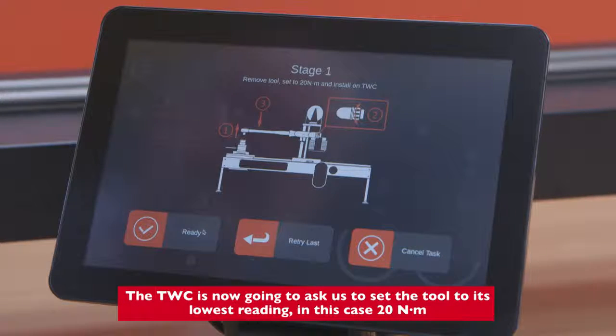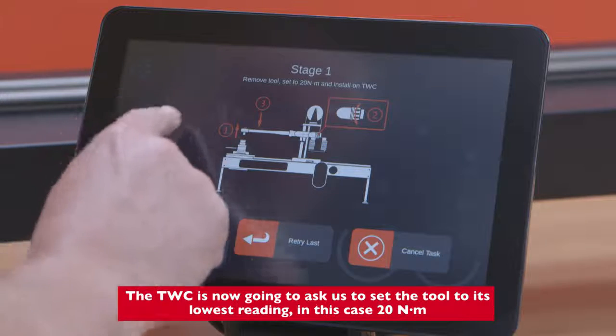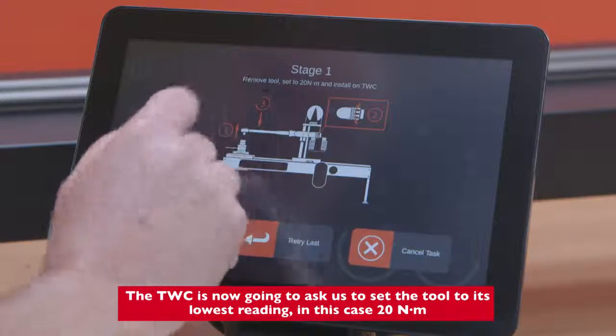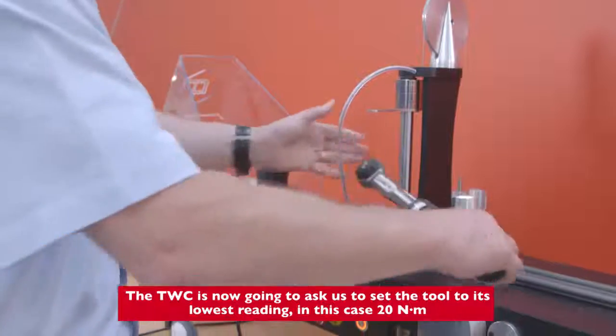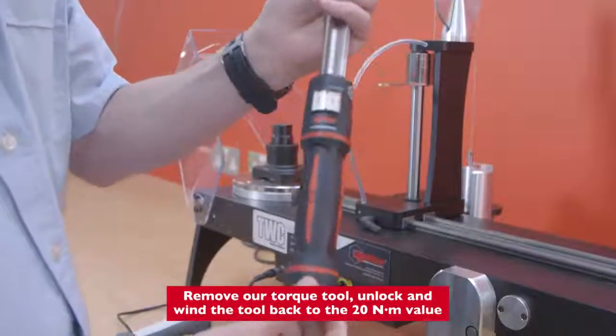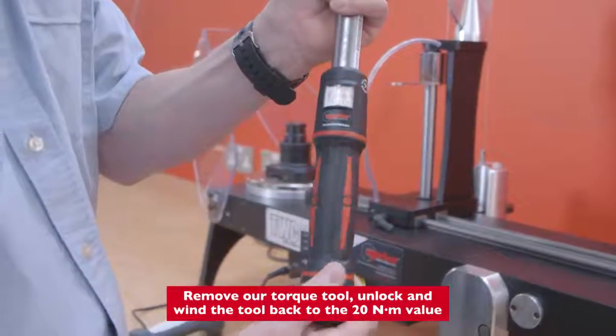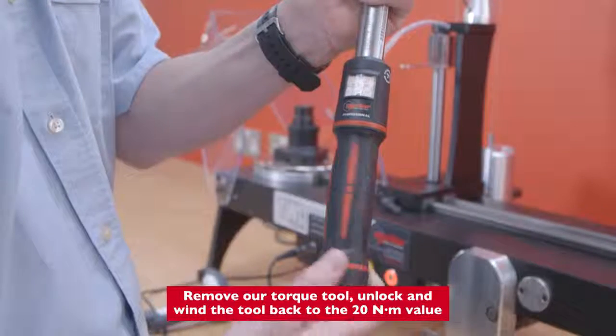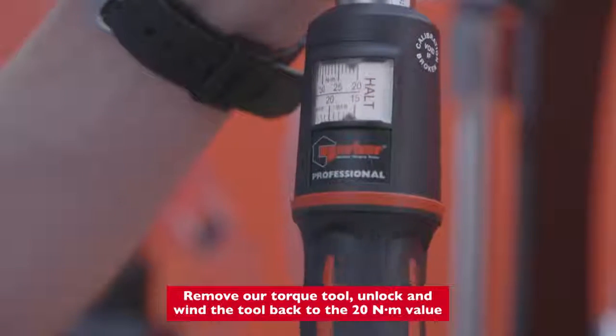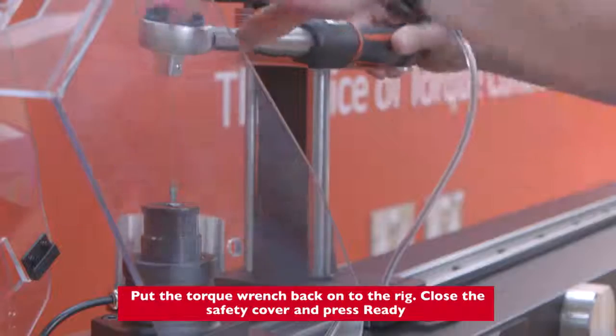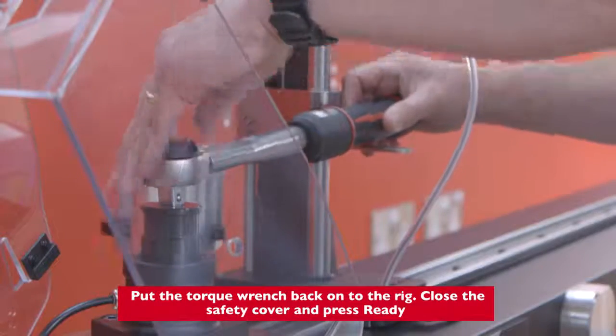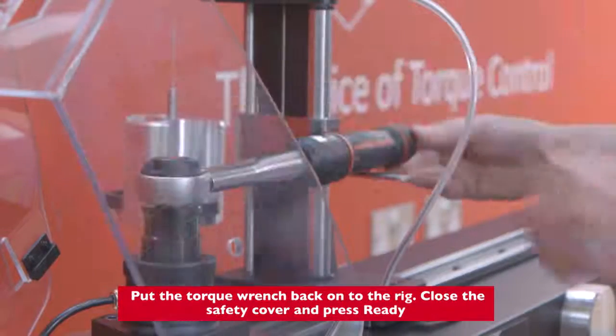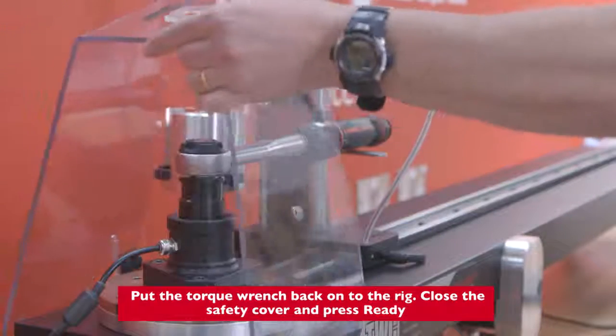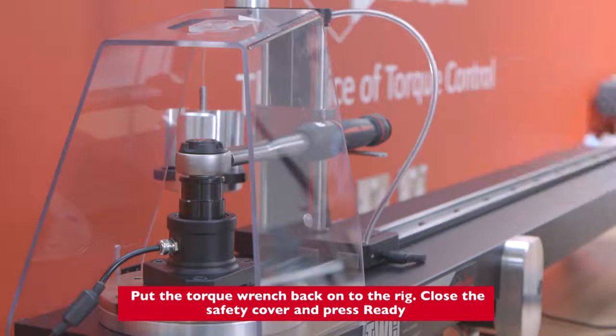The TWC is now going to ask us to set the tool to its lowest reading, in this case 20 Newton meters. Remove our torque tool, unlock and wind the tool back to the 20 Newton meter value. Put the torque wrench back onto the rig, close the safety cover and press ready.